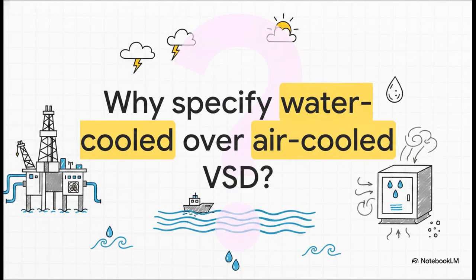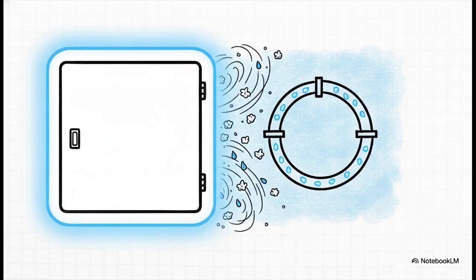Lots of drill ships specify water-cooled variable speed drive cabinets instead of the standard air-cooled ones. Why would you want to introduce water cooling into a room full of live, high-voltage electronics out on the ocean when air cooling is so much simpler? Think about what air cooling actually means out there. Did you guess it? Air cooling means drawing ambient marine air, packed with humidity and corrosive salt, straight across your live critical electronics.